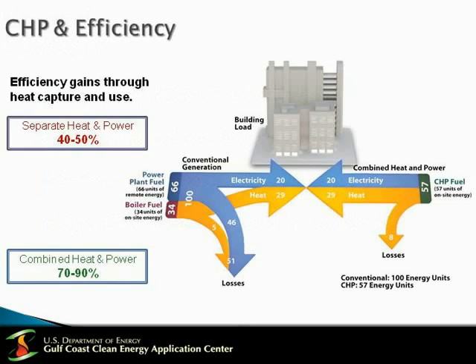Now let's look at this imaginary building which requires 49 units of energy, 20 units for electricity and 29 units for heat. On the left-hand side is your conventional generation, which consists of a power plant to produce electricity and an on-site boiler fuel. To supply the 49 units, you require 100 units of energy. On the right-hand side is the combined heat and power system, which supplies the same 49 units of energy required by the building with 57 units of on-site energy.